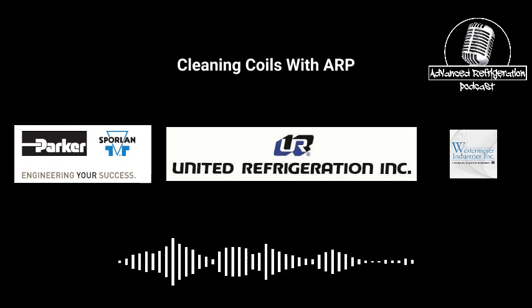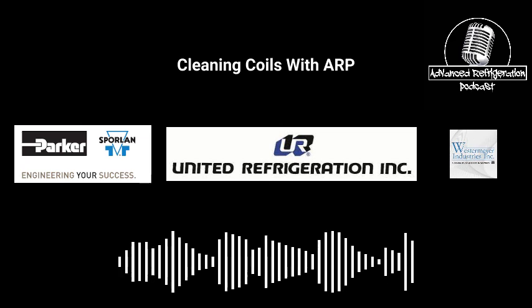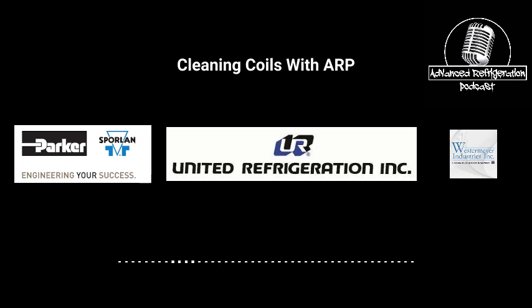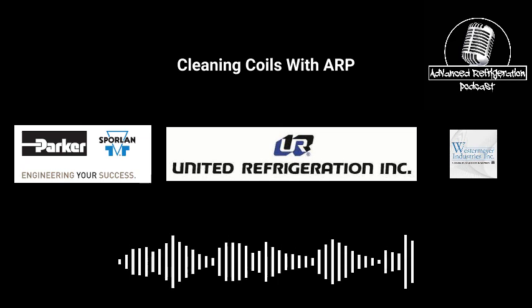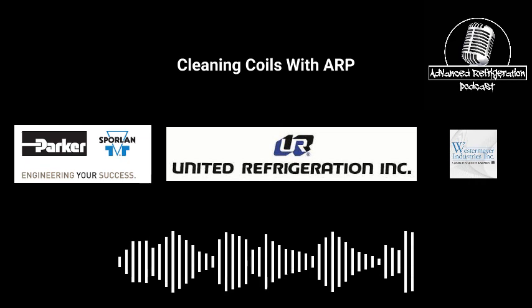And then you're going to have to keep power washing. You may have to do it 2 or 3 times in order to get all that debris in the center condenser and those center tubes cleaned. Because what's happening is those center tubes and center fins are all blocked up with calcium or dirt, and they're not exchanging any heat. The passages are blocked up so that air's not going through there, so you're not getting proper airflow.